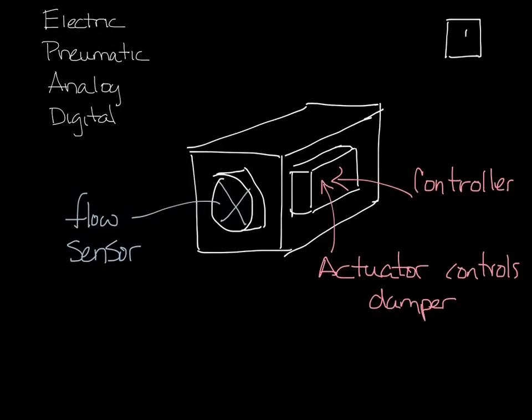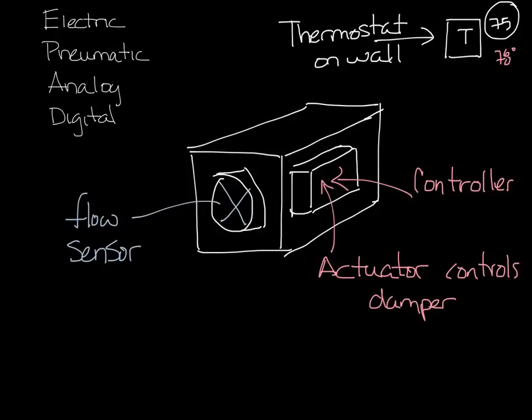Somewhere in the room there'll be a thermostat. The thermostat sets the set point and measures the room temperature. So say you have a set point of 75 degrees and your space is 78 degrees. It sends that information to the controller. The controller then says, hey we need more air and it'll send it to the actuator to open the damper.